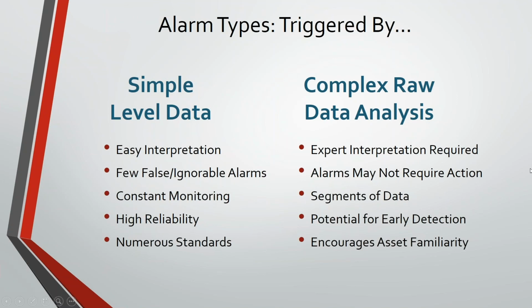So simple level data is generally easier to interpret, and that's a big deal. If you've already got a preset alarm, if you're following standards for your industry, you know what to do when the alarm goes off. You might have already caused some damage to your equipment when this alarm goes off, but at least you are taking care of the really important stuff. You're taking care of your personnel, and you're keeping your assets in hopefully good enough condition that you can repair them quickly and get them back up and running as fast as you can.